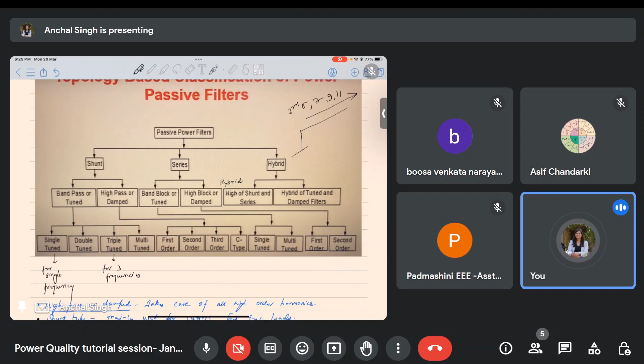But there is another case in which I know that there are third, fifth, seventh, ninth, 11th, all the higher order harmonics, the odd ones. If I get this kind of system, will I put a compensator for each and every one of these frequency components? No, right? It will be very expensive. So I would instead just put a high pass filter there, right? I tune this high pass filter such that its cutoff frequency is less than the third harmonic frequency and greater than the fundamental frequency. Then all these harmonics will be taken care of. So this is called a high pass or damped filter. That is the category.